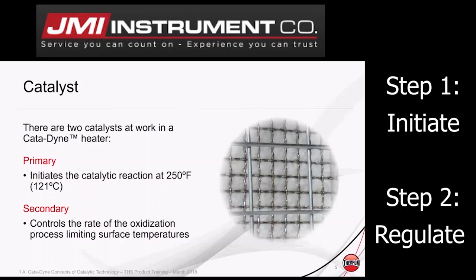We have to control the rate of the catalytic reaction — or control the rate of oxidization — to limit the surface temperature and keep the surface temperature where it needs to be, especially when we're dealing with temperatures within a classified area. So that's the primary and secondary catalysts, all encompassed into the catalytic pad in general.